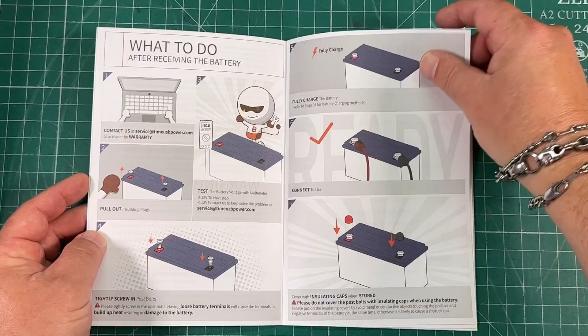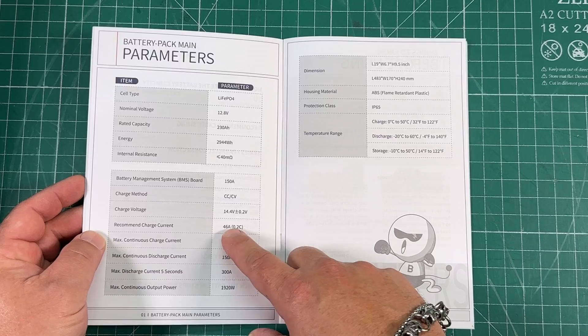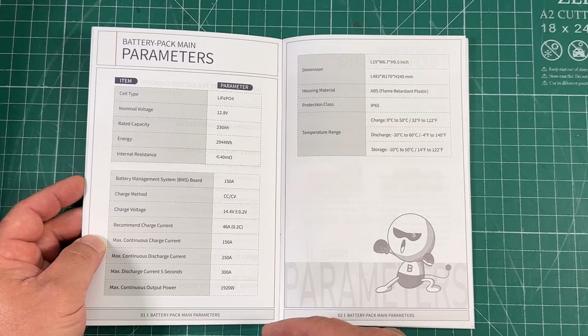Here we have the battery pack main parameters: lithium iron phosphate, your voltage, your capacity, the BMS again 150 amps, constant current constant voltage charging, charge voltage 14.4 plus or minus 0.2 volts, and again 150 amps, 300 amp max discharge current for 5 seconds, so that's cool.